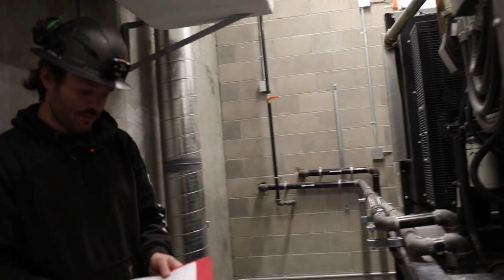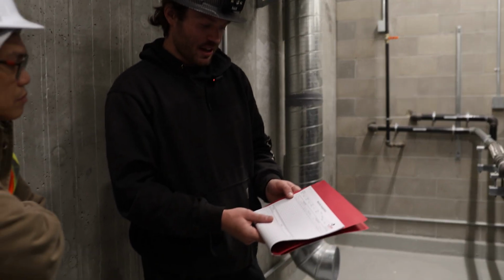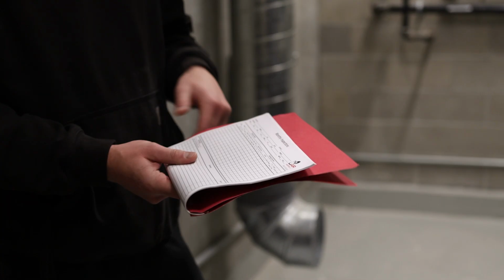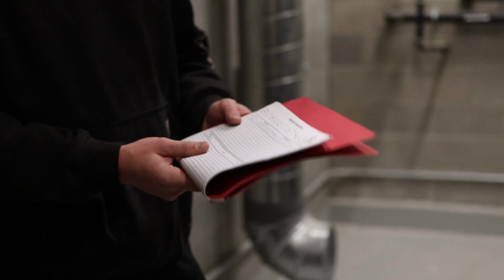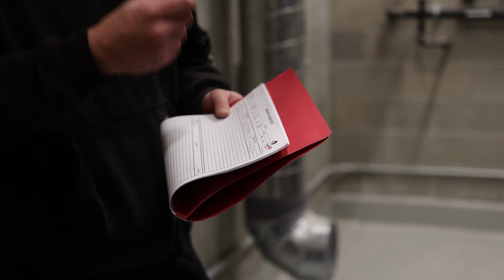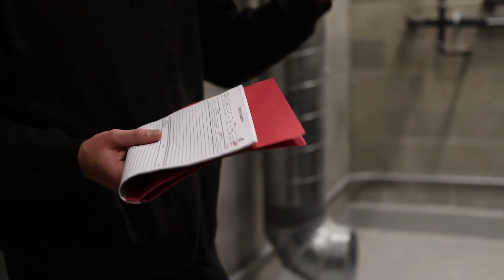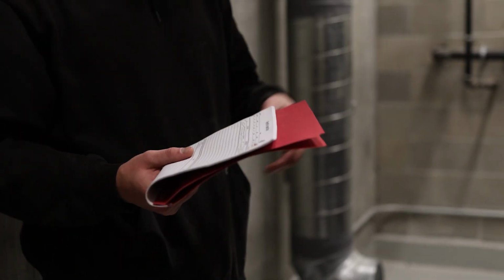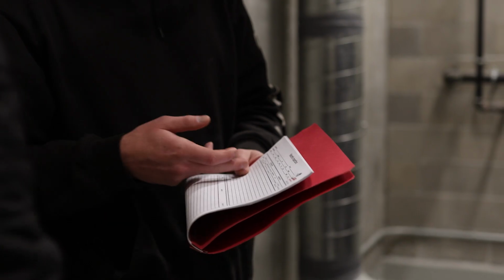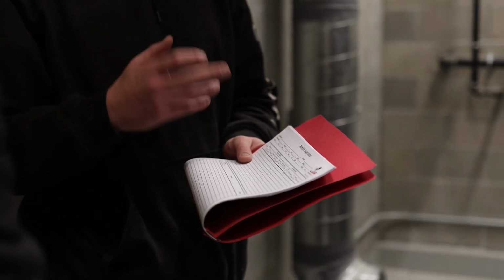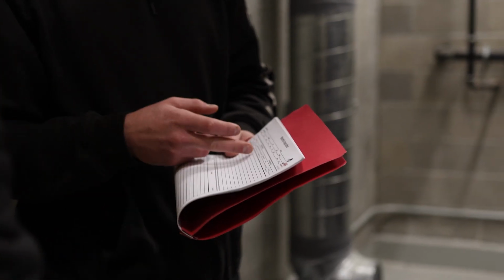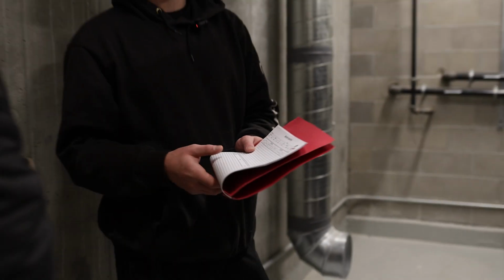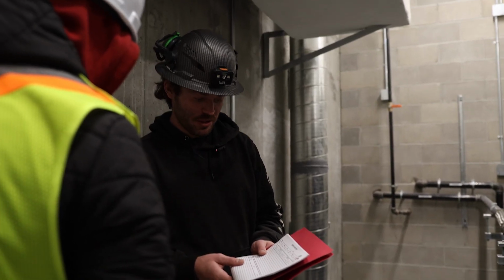But first thing will be recording of the date, the hours before, the hours after, your fuel level, your oil level. It could be just a check mark, your coolant level, check mark, coolant rated. It's minus 40 rated coolant in the thing. And battery level, that's not applicable because there's sealed batteries on this guy. Lamp test, basically make sure all the indications are working and flashing as they need to be.